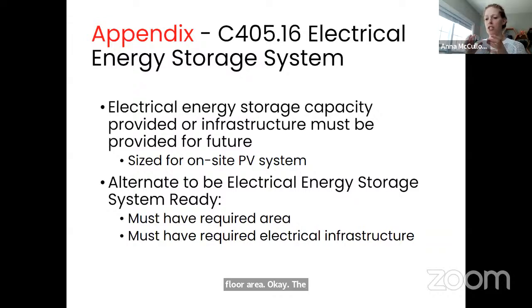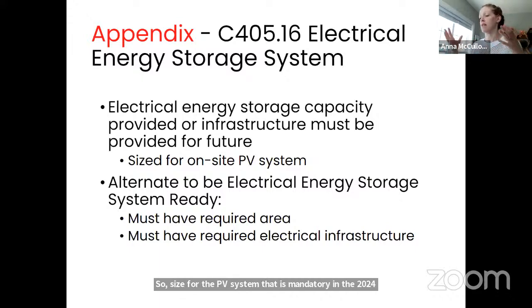So each project would have the opportunity, if you adopted this appendix, to essentially provide the energy storage system required sized for the PV system that is mandatory in the 2024 IECC, or provide future storage square footage in the building, as well as the required electric infrastructure. So they could essentially haul in some batteries, provide the fans for ventilation, and plug them in, and they should be good to go. Does that clear it up a little bit for you?